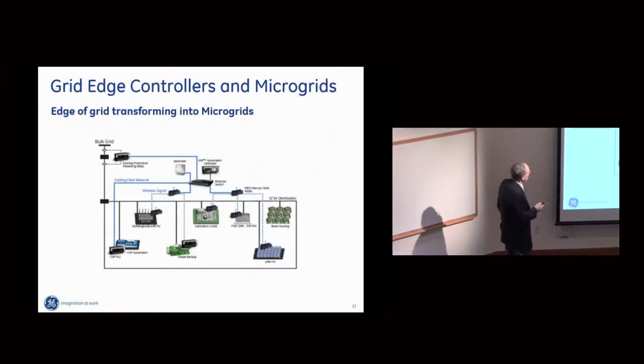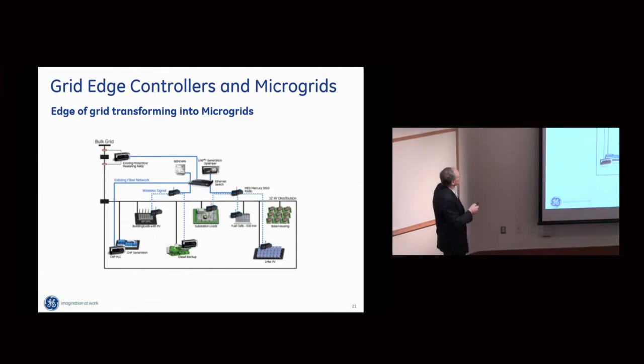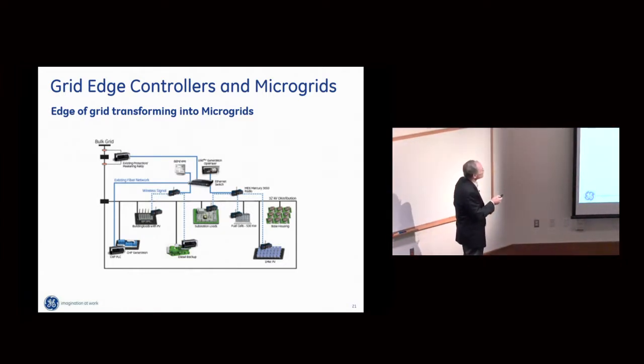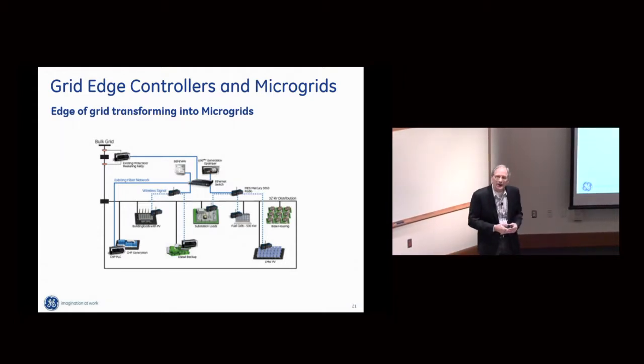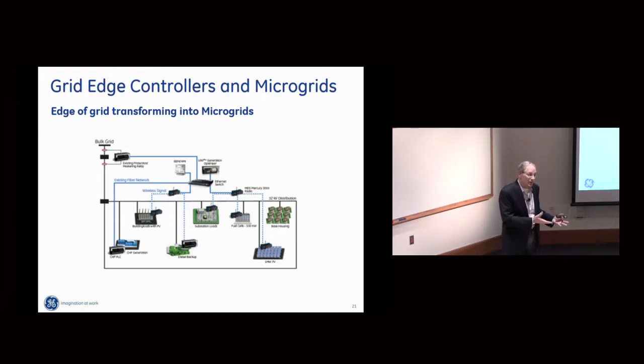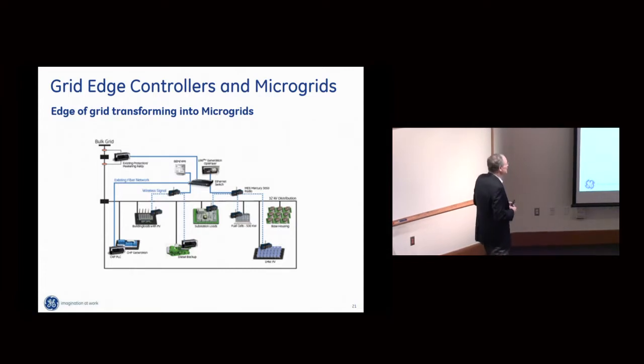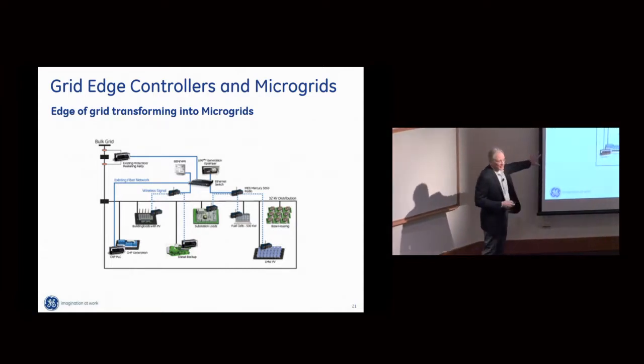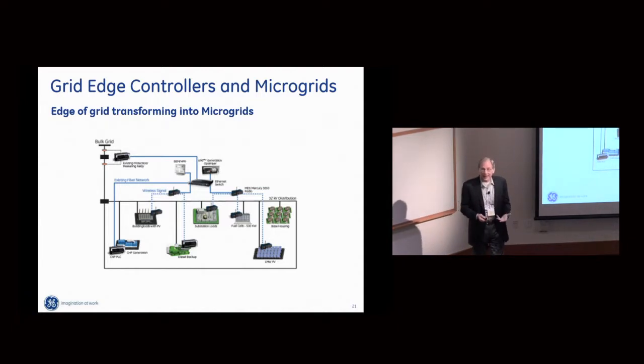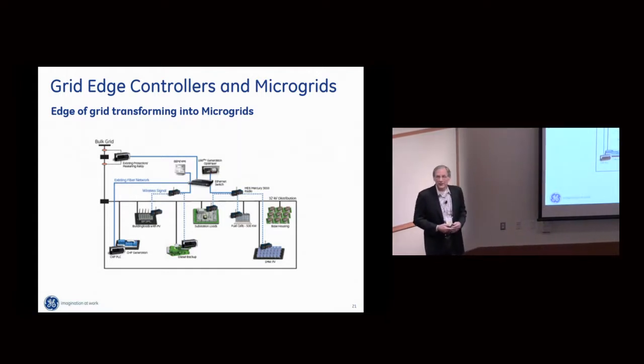This is a family of new devices we call grid edge controllers on the low voltage network. In areas with high penetration of photovoltaic panels on homes, we have a lot of volatility on that low voltage network when you have high penetration, and we need to address that volatility there. We don't want it to propagate up into the grid. So Varentec is one company that has these low voltage network dynamic grid edge controllers.